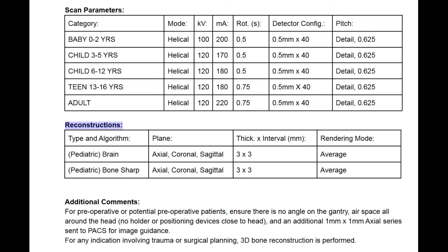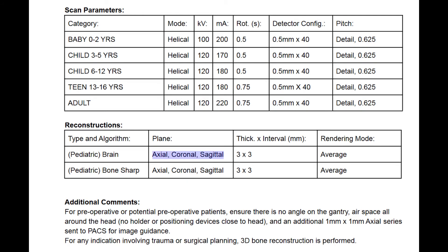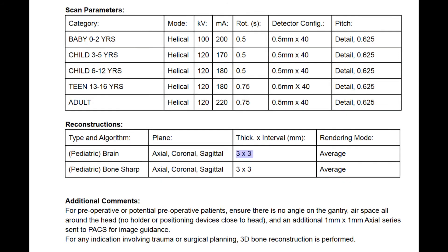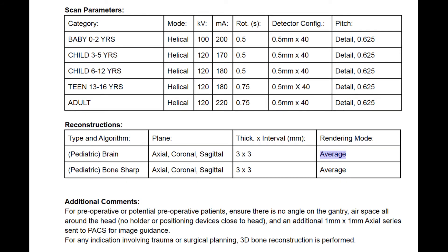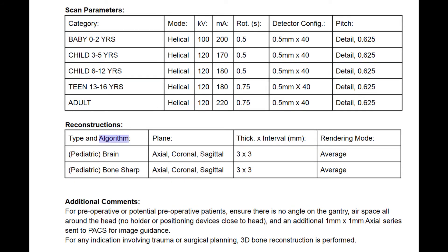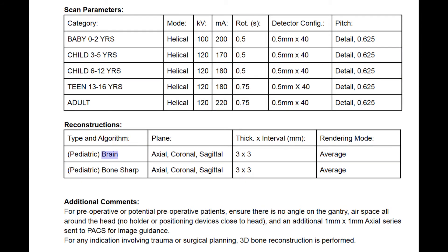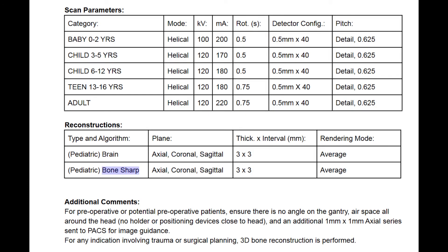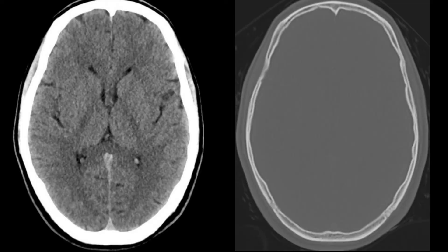Moving down to the reconstructions, we're not sending those 0.5 millimeter slices to PACS. We're going to send three planes — axial, coronal, and sagittal — with three millimeter slices at three millimeter intervals, so three by three. They're rendered using volume averaging, so each three millimeter cubic voxel represents the average measured density in that area. We process this with two different filters, or kernels: a brain filter, which is relatively smooth to reduce noise and improve contrast resolution for grey and white matter differentiation; and a sharp bone filter, which improves spatial resolution to highlight tiny fractures or inconsistencies in the bone and show those tiny ossicles in the inner ear. The raw data goes through two different processing algorithms and the image data is built into axial, coronal, and sagittal planes before being sent to PACS.